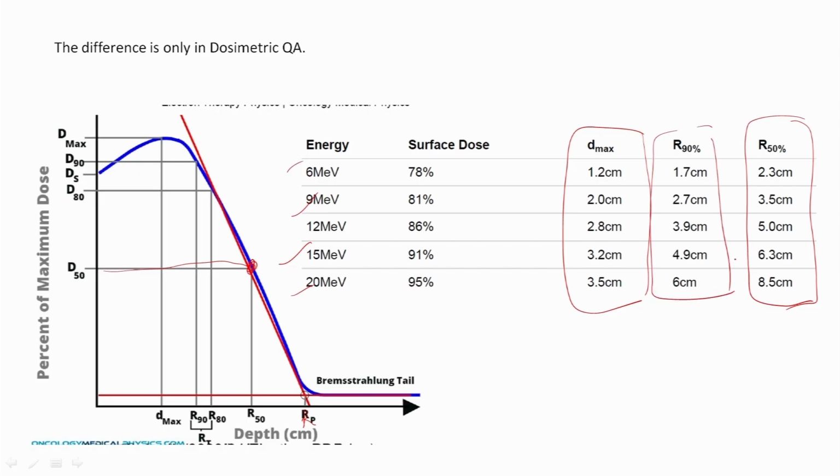So you can see that the quality assurance tests for electron are the same, except for minor changes for the absolute dose measurement as well as for the optical and radiation field congruence. In this case, you need to insert the applicator for the measurement of optical and radiation field congruence. All other mechanical tests which we perform for the photon beam are the same in case of the electron beam, keeping these small changes. So we will continue our remaining LINAC quality assurances in part 2. Thank you.